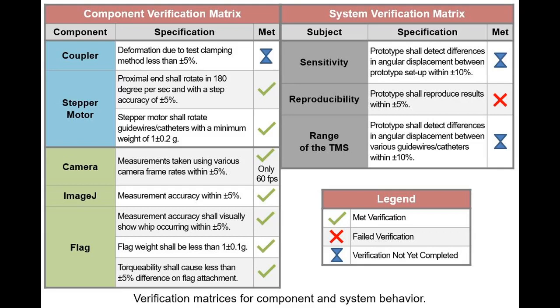For a prototype to pass the predicate equivalency argument, the prototype and the commercially available device should be tested in the 3 pathway configurations, and for 2 of the 3 configurations, the angular rotation for the 2 devices should be within 10% of each other. The prototype can then be sent to a third-party company for final testing. Otherwise, the prototype must undergo design revision.